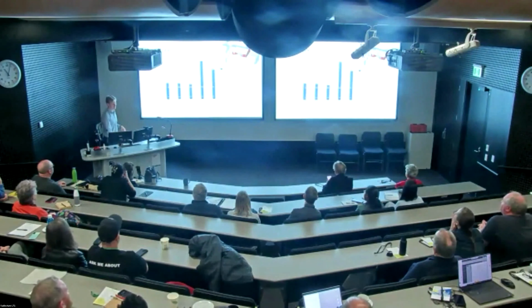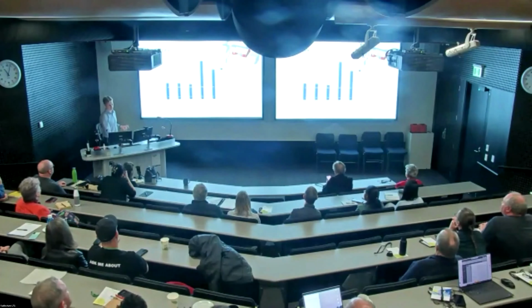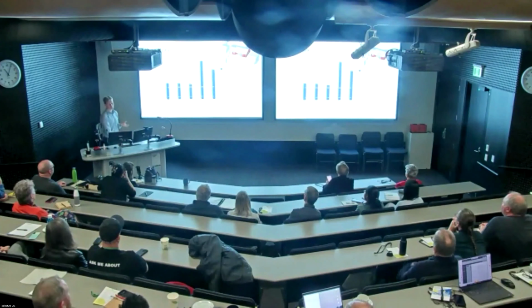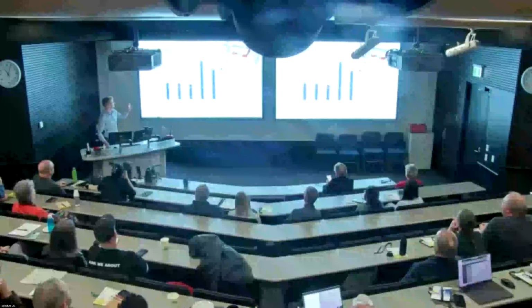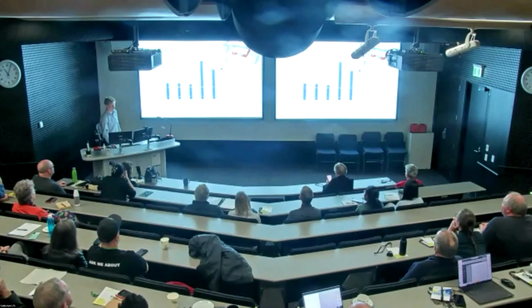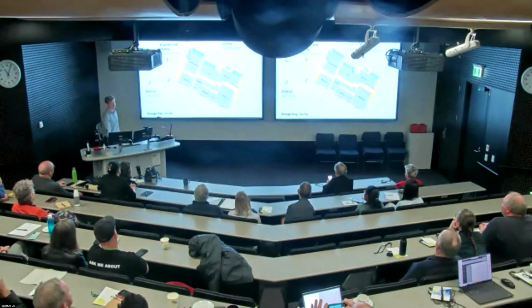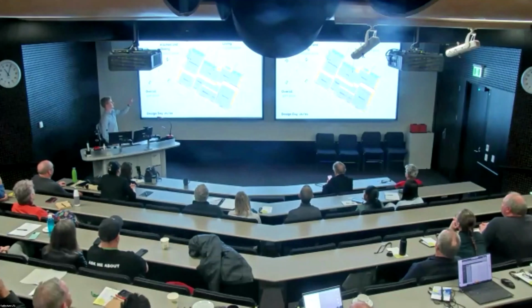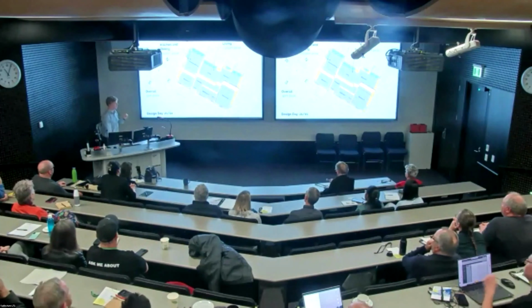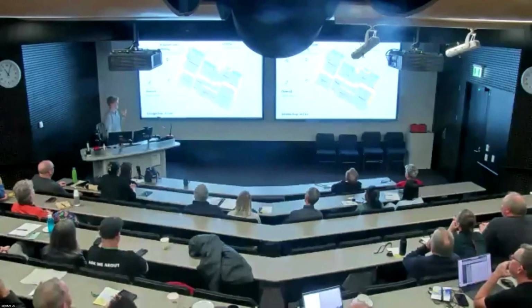Looking at standalone 2, the kitchen and living spaces have considerably higher cooling intensities than the other spaces. We see good alignment between the adjusted PHPP and the single zone model, the lines almost on top of each other. The reason the kitchen, dining and living spaces have much larger intensities is mostly to do with the glazing. In particular, this kitchen and dining area has a corner with glazing on the north and west, and it's just getting absolutely hammered in the mid-afternoon, and that's why it's so high.